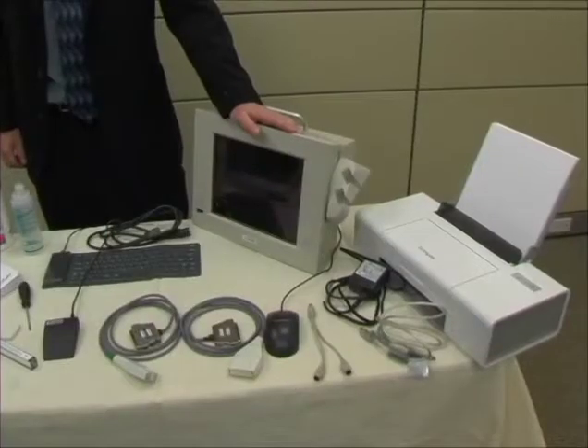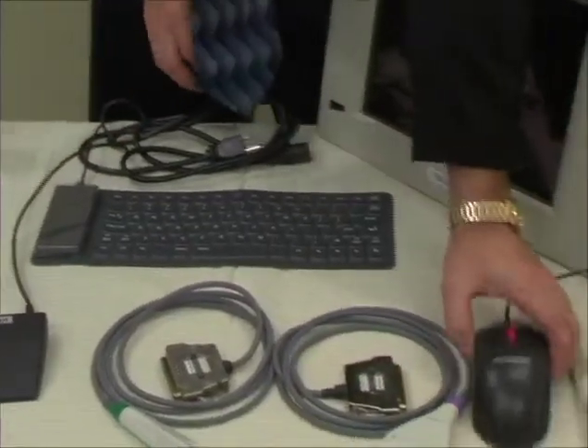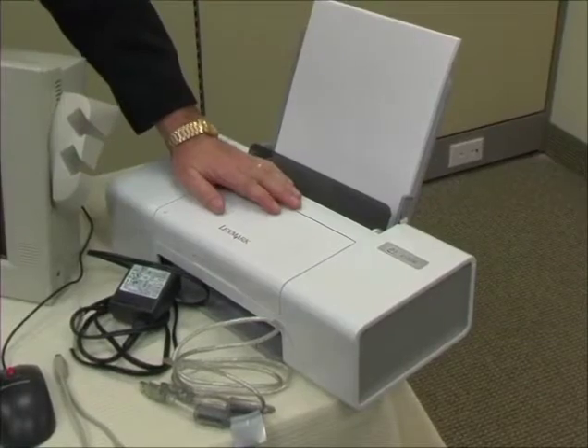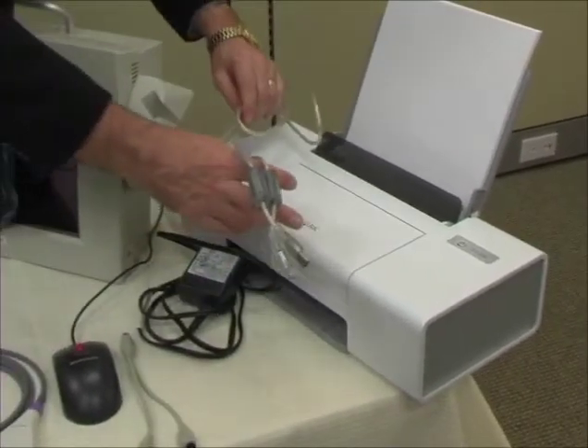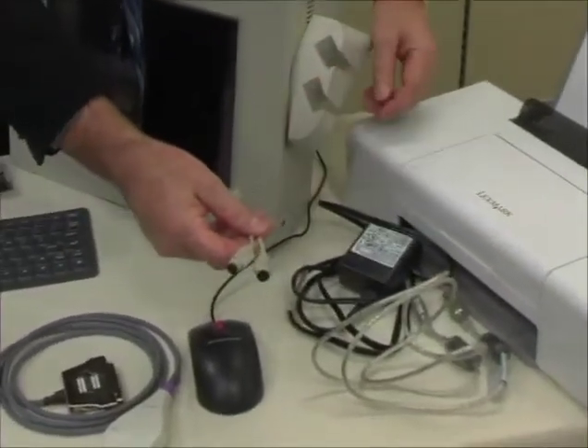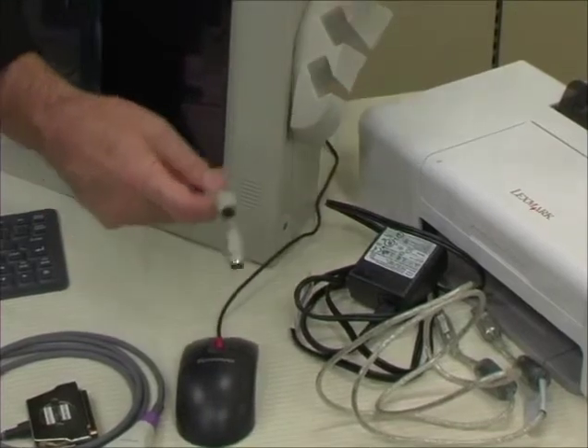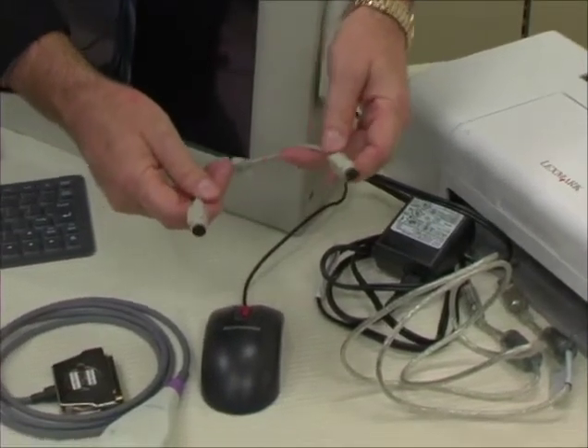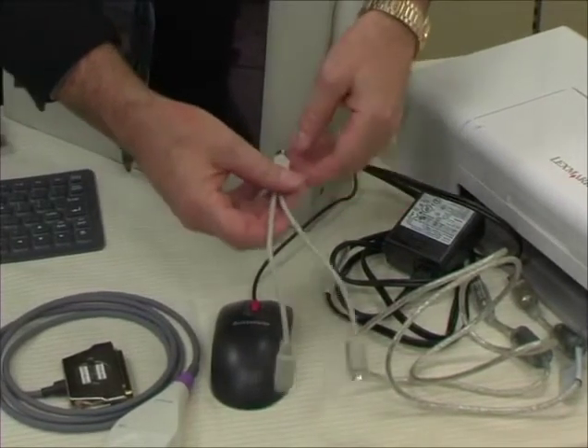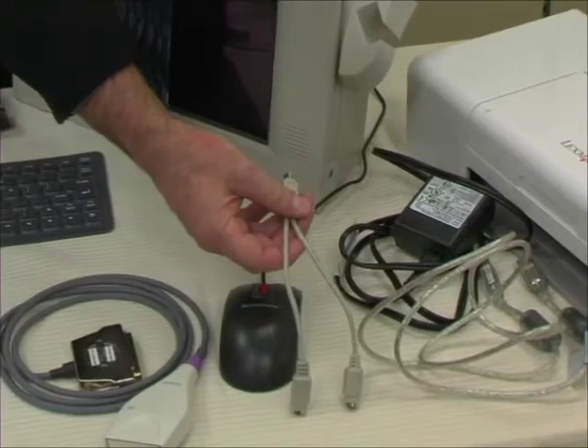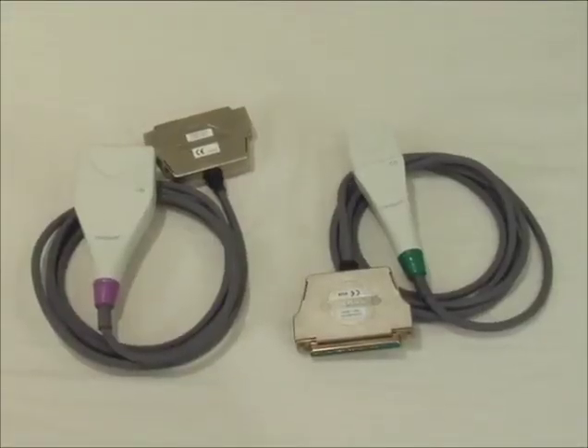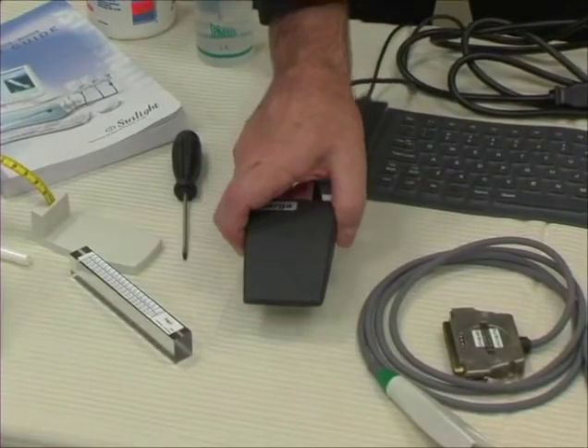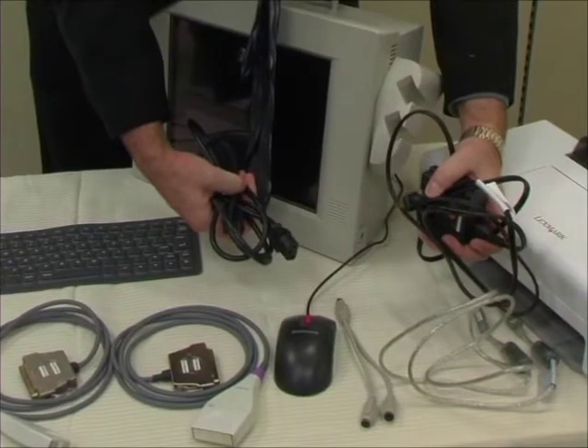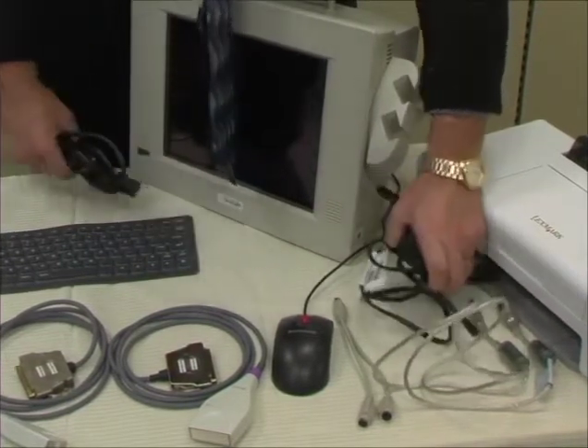So first of all, what we want to do is ensure that all the components are accounted for that we'll need to run the test. So we have the Sunlight OmniSense unit, we have a keyboard, we have a mouse, we have the printer, and we have all the connecting cables. And an adapter. The adapter will be used to connect the mouse into one receptacle, the printer into the other receptacle, and then the main receptacle into the unit itself. We've already mentioned the two probes, which we do have. We have a foot pedal, and we have two power cables. One power cable is for the unit itself, the other power cable for the printer that we're using.